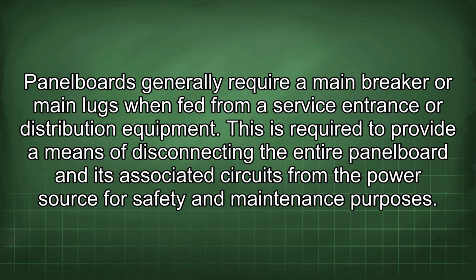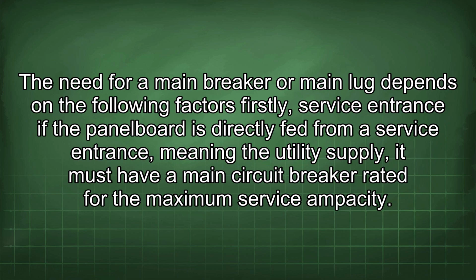Panel boards generally require a main breaker or main lugs when fed from a service entrance or distribution equipment. This is required to provide a means of disconnecting the entire panel board and its associated circuits from the power source for safety and maintenance purposes. The need for a main breaker or main lug depends on the following factors.